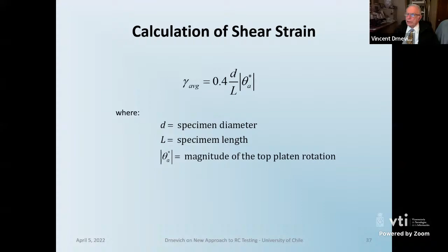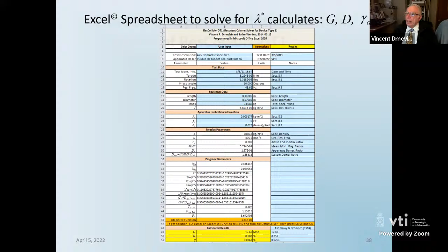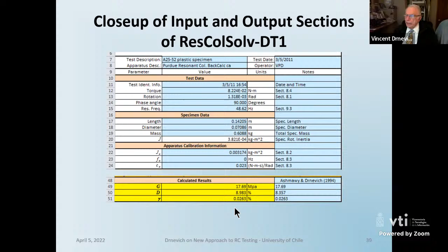All right, now this is something in the ASTM standard that's written for this, ASTM standard D4015-21. This is a spreadsheet solution that does all of that for each data point. And I'll expand here a little bit. What you do is you put in the test identification, the torque, the rotation, the phase angle. That could be 90 degrees if you're at resonance. It's something other than that if you're off resonance. And you put in the resonant frequency or the actual frequency. You then enter the specimen length, diameter, mass, and the polar mass moment of inertia of the specimen, and it will calculate some intermediate parameters, and then voila, you push the button and you get the modulus, damping, and strain amplitude directly.